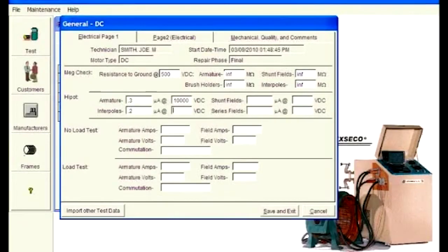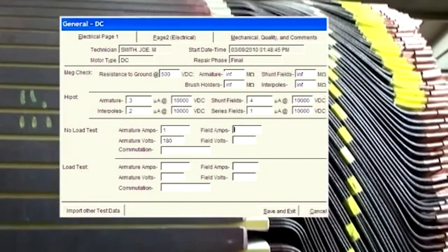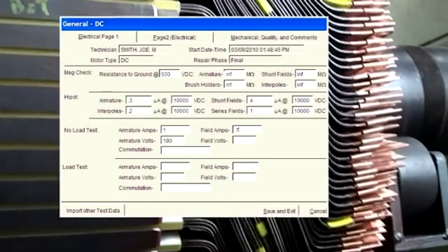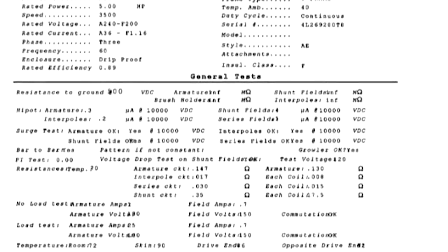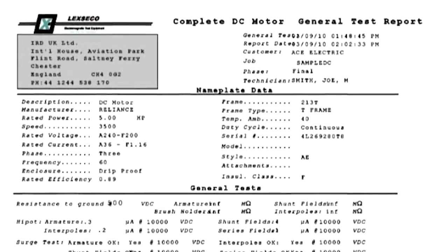There is also a facility to enter and save to the database general test data including winding resistance values, insulation resistance, test currents and temperatures. The Lexseco software also includes a winding verification program which provides a method of calculating winding data. Together this provides a convenient and comprehensive general test report on any unit in hard copy format.